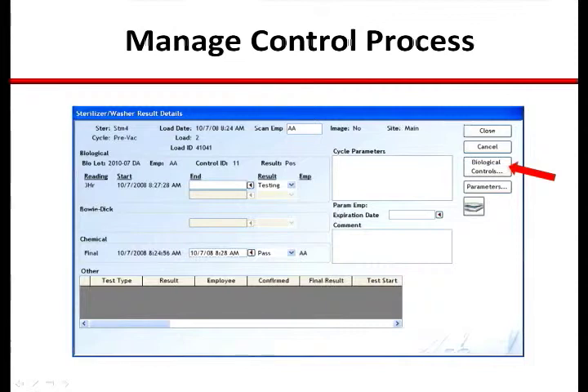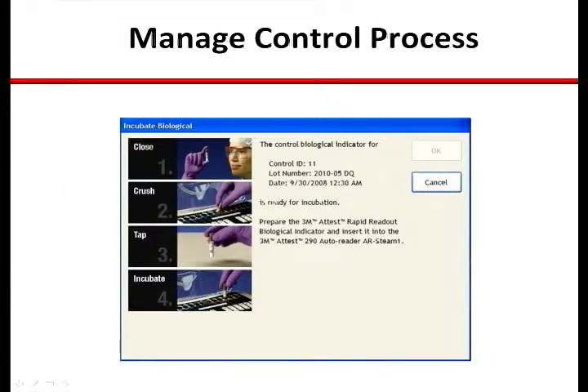The system will recognize when a control is needed based on the AutoReader in which the test BI was placed. Further, the system will correlate test BI lot number to ensure spore viability and will provide prompts and disciplines based on the recommended practice and instructions for use. Instructions for use for control BI will be provided with a prompt to place the control into an available well in the same AutoReader.